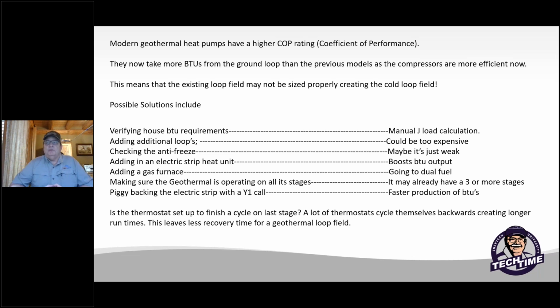The one other thing that we've seen a lot this year is making and verifying and checking that this heat pump is working in all of its stages. That's something we have found this year, that sometimes the thermostat wasn't programmed right, or the wiring was broke off or something this year, and we never were getting into even second stage geothermal operation, as well as if it had an electric strip, we weren't seeing the electric strip come on. So the important thing is, when you do your performance checks in the fall or the spring, make sure and verify everything is working properly the way that it should.